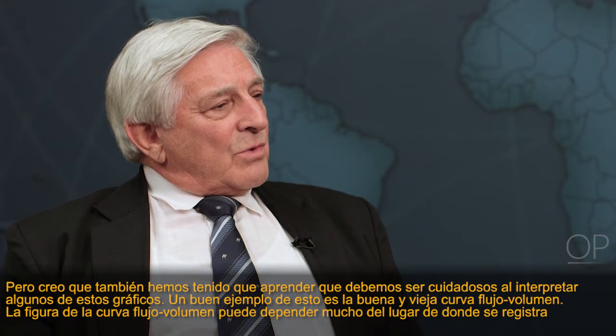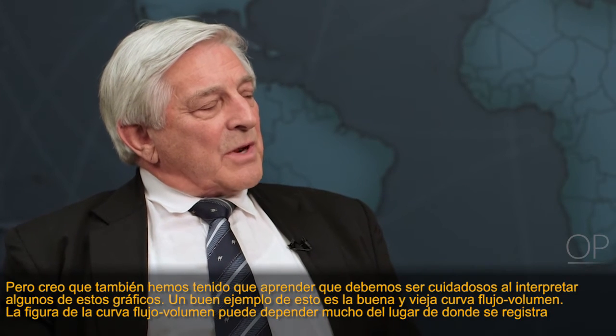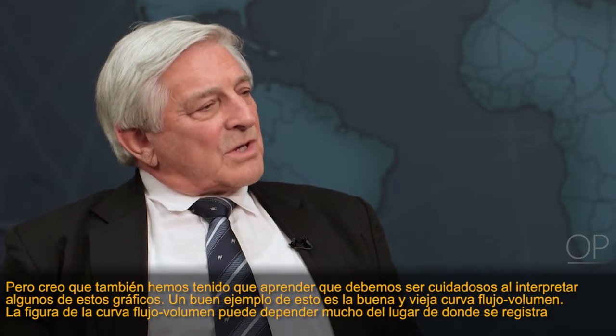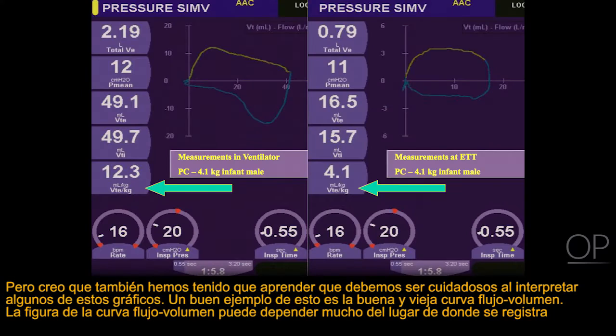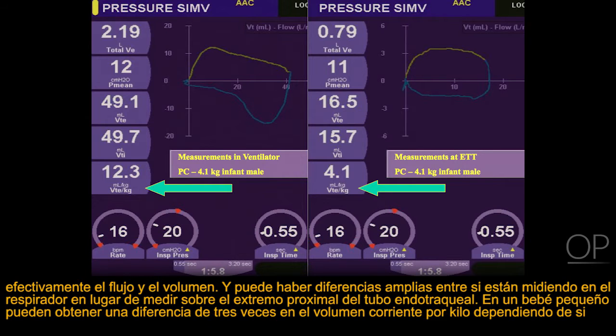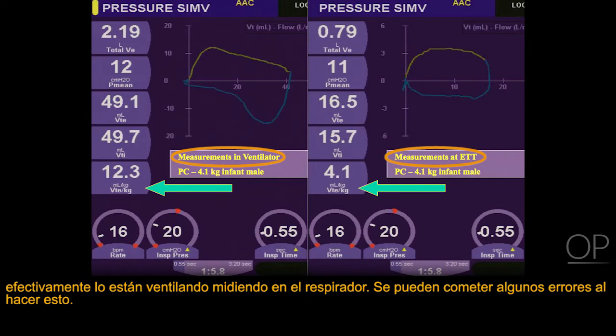But I think we've also had to learn that you have to have some caution interpreting some of these graphics. A good example of this is the good old flow volume loop. The shape of the flow volume loop may depend very much on where you actually record the flow and the volume from. And there can be vast differences between measuring it back in the ventilator as opposed to measuring it on the proximal end of the endotracheal tube. You can have a 3 times difference in tidal volume per kilo in a small baby, depending on whether you're measuring it back in the ventilator. You may make some mistakes doing that.